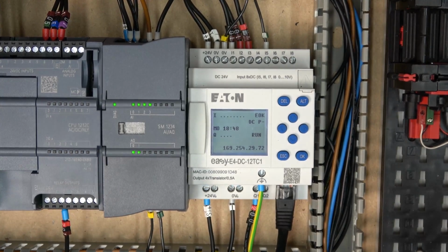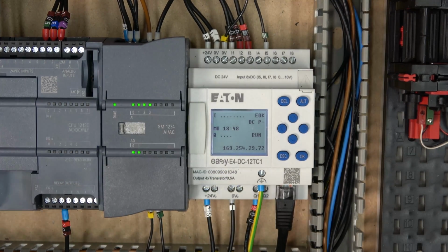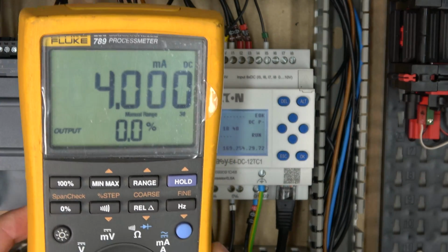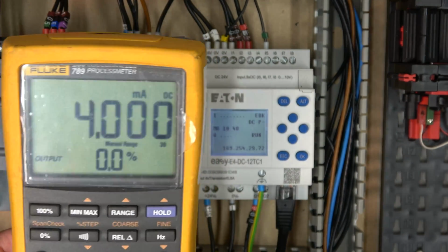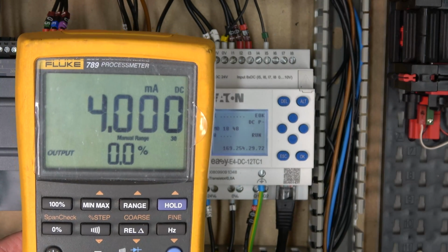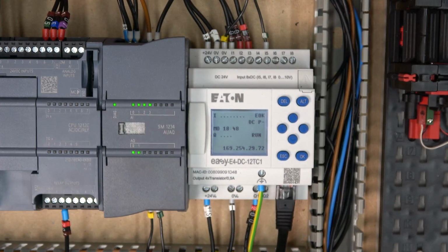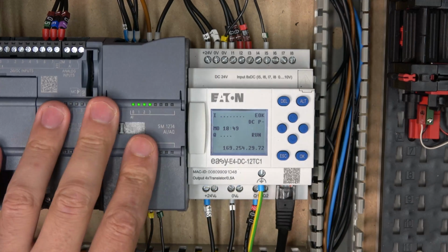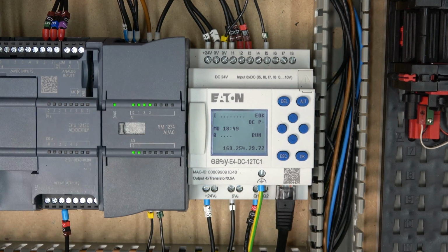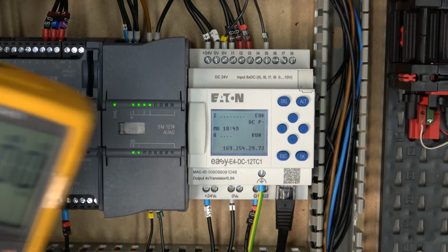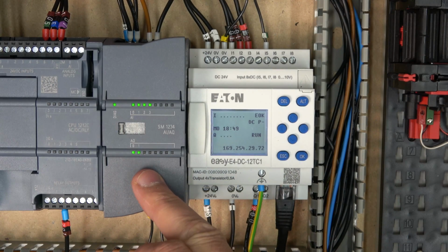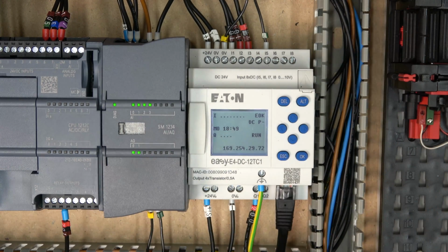So as usual, let's quickly check out how the wiring works. We're going to be using this Fluke process meter, and unfortunately this process meter cannot generate a 0 to 10 volts, so I had to improvise. I'm going to be using the help of a Siemens analog card, where I'm going to be sending in 4 milliamps. As you can see down there, it's 4 to 20 milliamps.